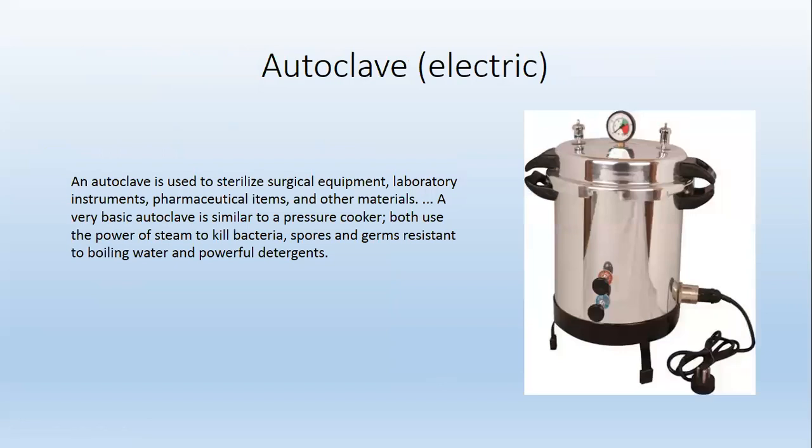Next is autoclave. An autoclave is used to sterilize surgical equipments, laboratory instruments, pharmaceutical items, and other materials. A very basic autoclave is similar to a pressure cooker. Both use the power of steam to kill bacteria, spores, and germs resistant to boiling water and powerful detergents.